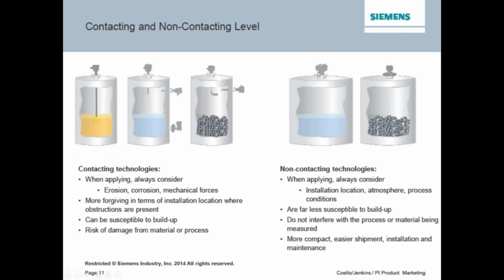Versus non-contact level measurement, like non-contact radar or non-contact ultrasonic, which we'll talk about today. One key advantage is you don't come in contact with the process in the tank, so you don't have to worry as much about things like material compatibility, buildup, corrosion, or mechanical forces from the product coming in contact with probes. So non-contact would typically be the preferred method when it will work for your specific application, compared to a contacting technology.